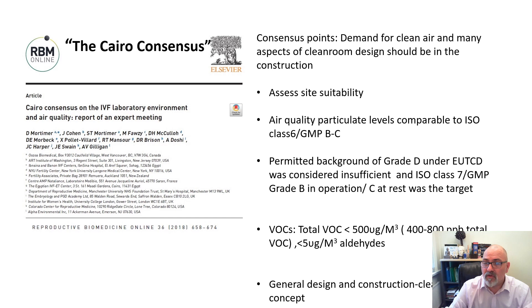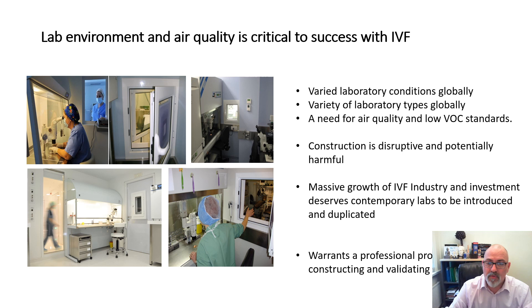The recommended air changes per hour were between 10 and 15. For positive pressure, the consensus recommends 38 to 50 Pascals. The background grade of Grade D under the EU Tissue and Cell Directive was considered insufficient — Grade B in operation and C at rest should be targeted. Regarding VOCs, total VOC level in the lab should be less than 500 micrograms per cubic meter. In conclusion, laboratory environment and air quality is critical to IVF success, and construction and renovation warrant a professional process of designing, constructing and validating IVF laboratories.